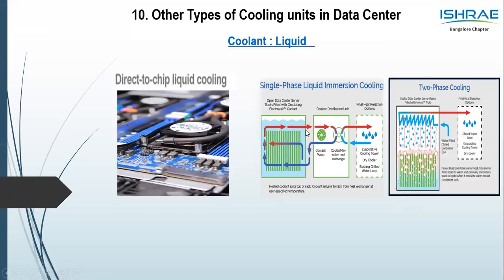The second concept is where the servers are dipped in coolant. With single-phase immersion, the coolant is taken back to the coolant pump and, with the help of a dry cooler or a heat exchanger, or even connected to chilled water, the coolant is taken back to the server, which is dipped in the coolant. Or it can be two-phase, where the coolant cools the server, and the hot liquid is then vaporized and condensed back to liquid form. So these are the two concepts we find in immersion.